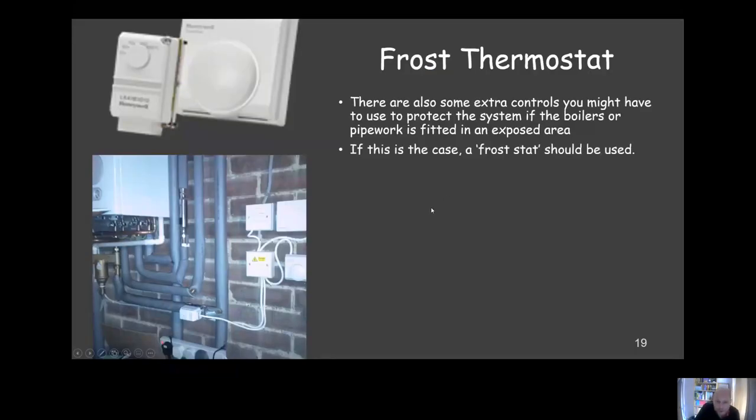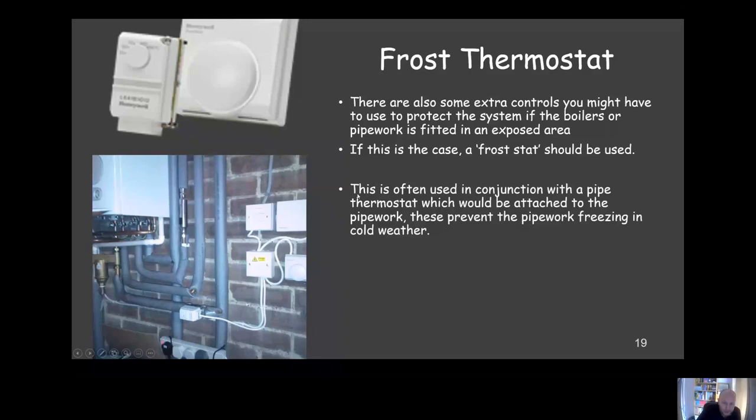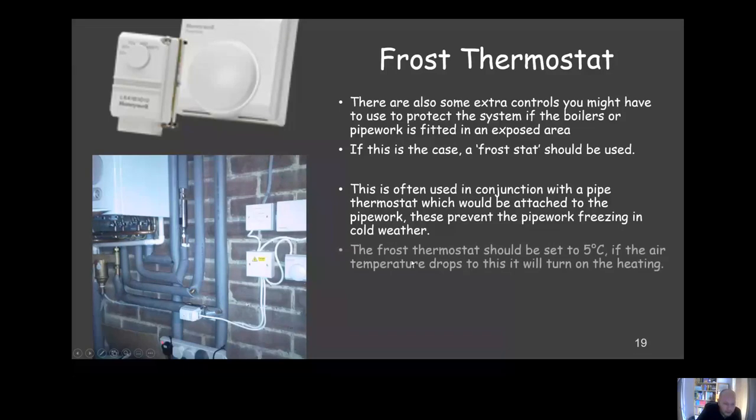Frostat. You may come across this if you ever have to fit a system in a garage, an unheated area of the house, or an attic possibly. You'd fit a frostat alongside a pipe stat. The frostat measures the temperature of the air, and it will automatically cause the boiler to fire up when it starts to get cold, about 5 or 6 degrees normally. And that's to help protect the pipework so it doesn't freeze.